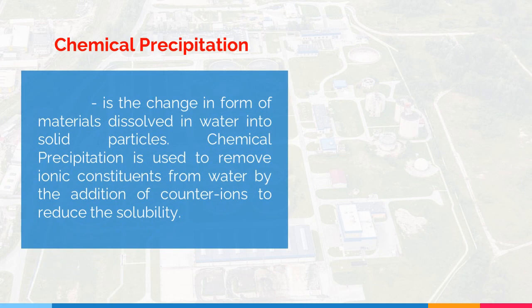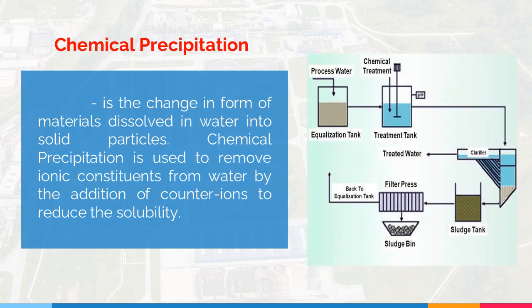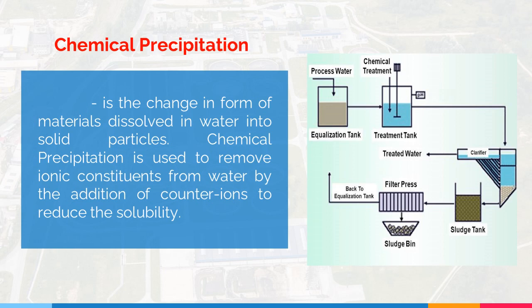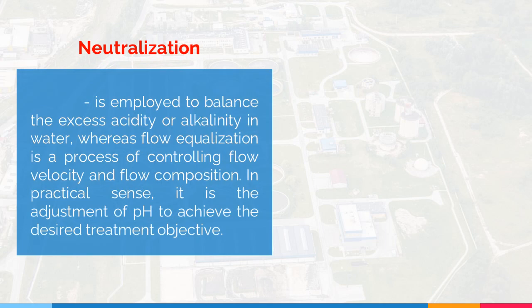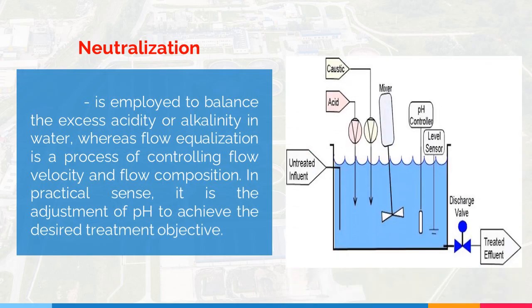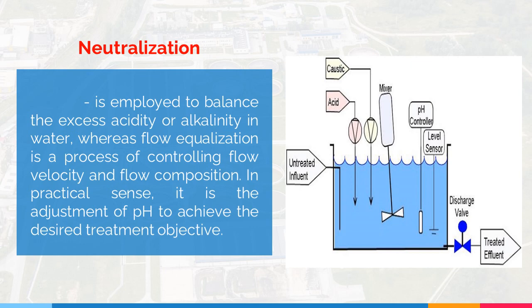Next is chemical precipitation. Chemical precipitation is the change in form of materials dissolved in water into solid particles. Chemical precipitation is used to remove ionic constituents from water by the addition of counter ions to reduce the solubility. Next, we have neutralization. Neutralization is employed to balance the excess acidity or alkalinity in water, whereas flow equalization is a process of controlling flow velocity and flow composition. In practical sense, it is the adjustment of pH to achieve the desired treatment objective.